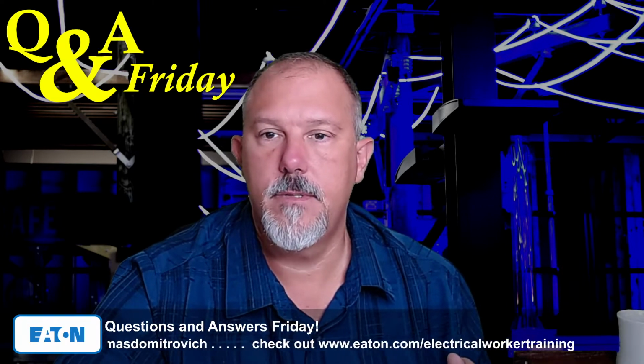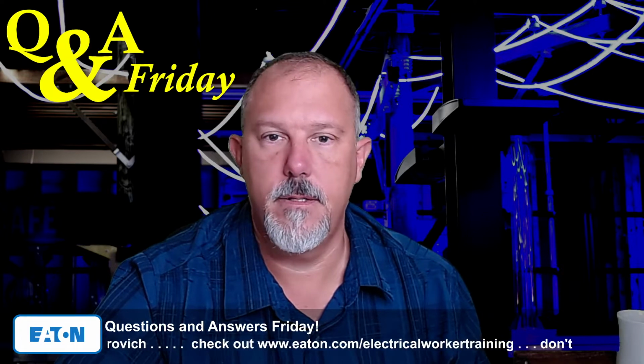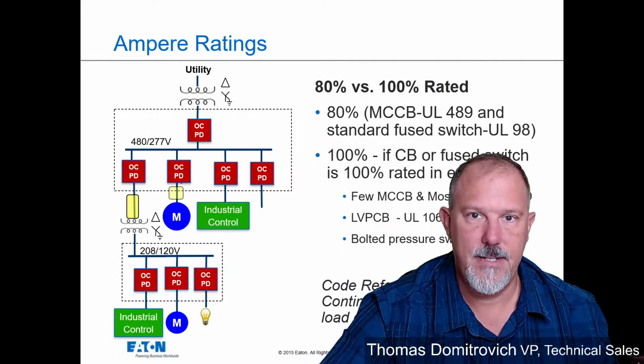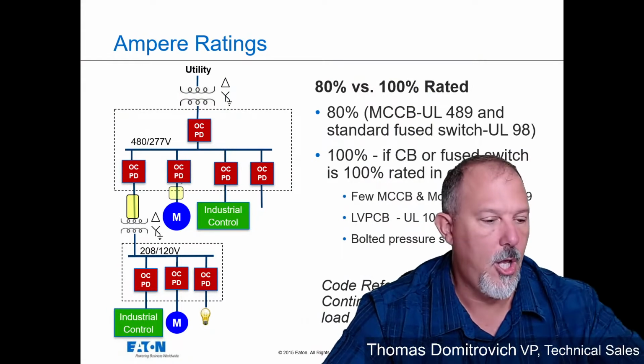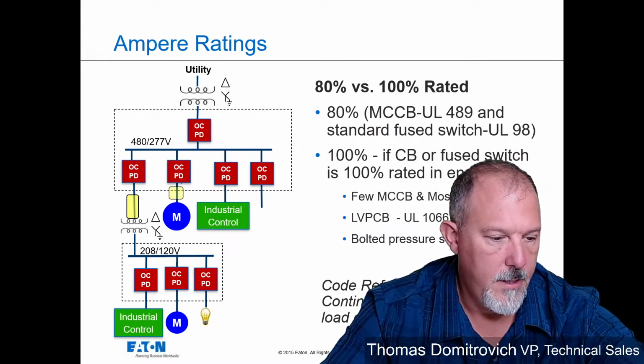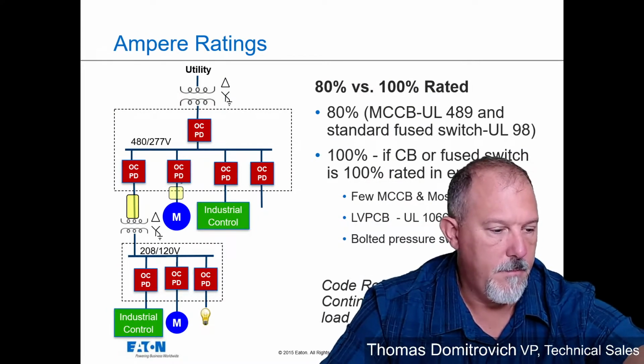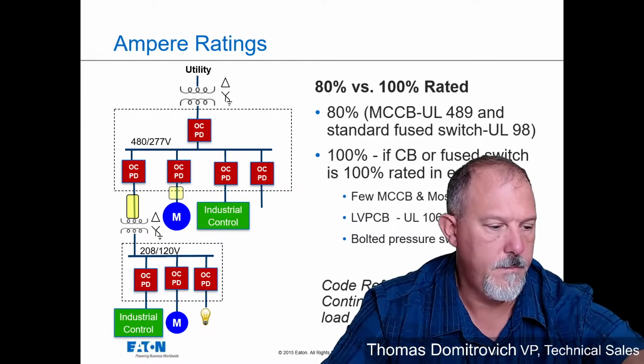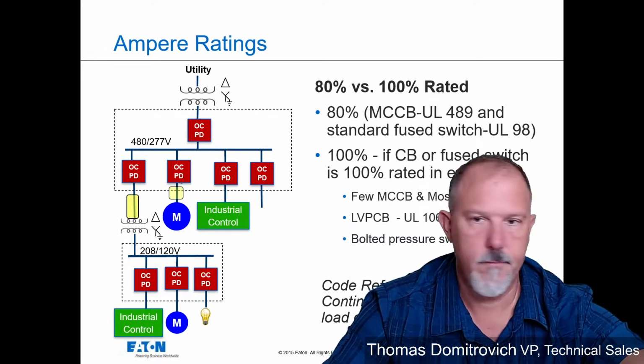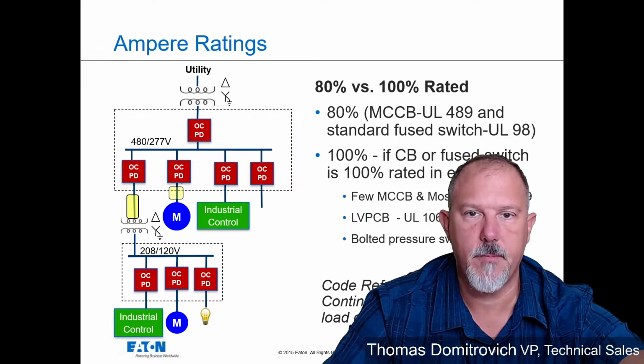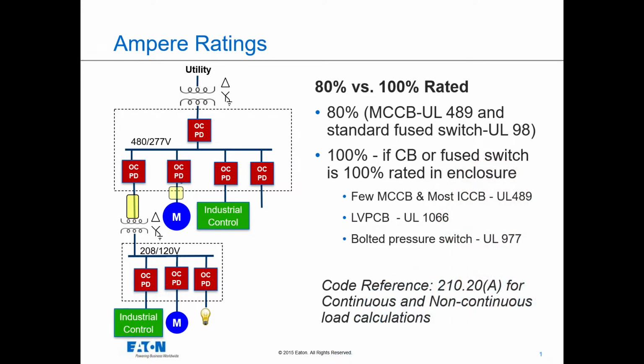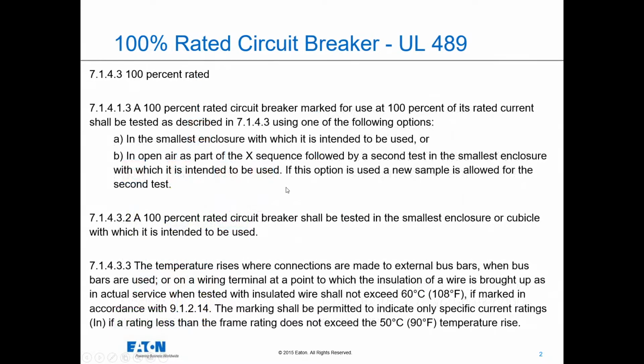All right, so let's take a look at this. 80% rated breaker, 100%. Here we go. Code reference 210.20. I'm just going to flip down through some slides here. This is out of how we test the breaker in UL 489.